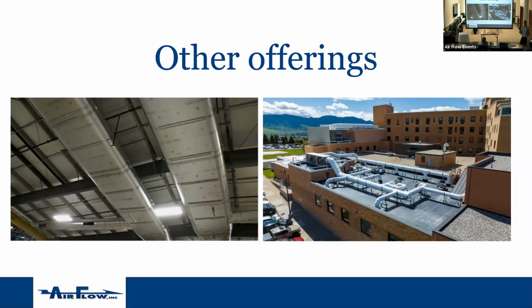The purpose of all this is to say systems leak. The white finish is great, but at the end of the day, what is the point of all this? If you choose that your systems leak less, this is an appropriate option. There are lots of things you can do in your duct systems to prevent them from leaking. If it's really $16 or $12 a CFM, then this is cheap. Think about coming back into a building and redoing the ductwork, you never can get a payback on that. So building it right the first time is probably a pretty great investment.